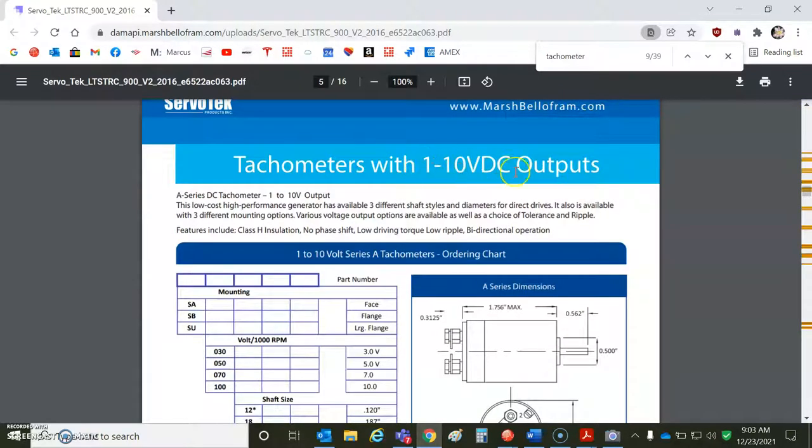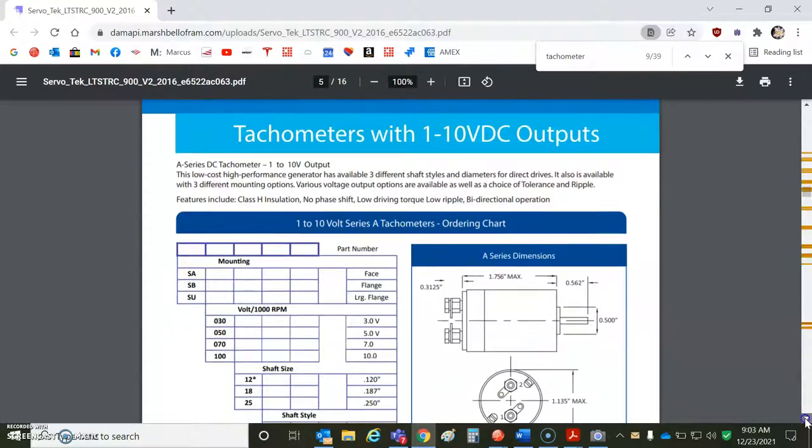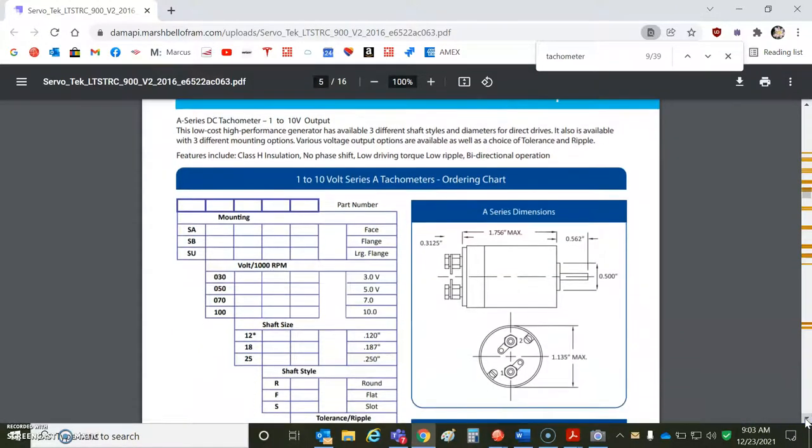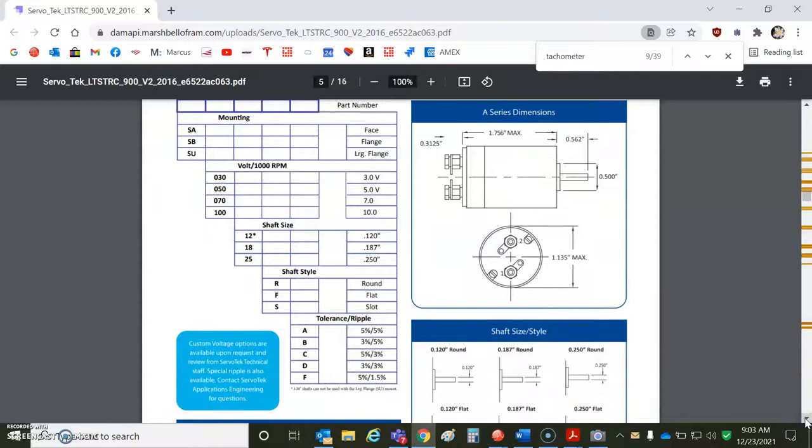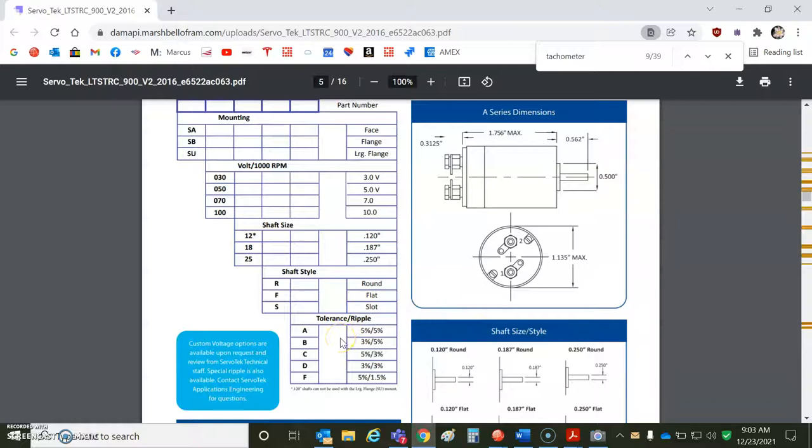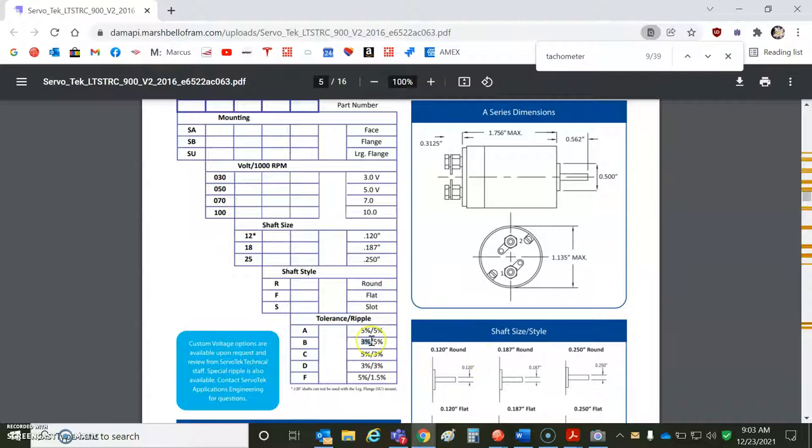Here's a 10-volt output. So when you're spinning at 1,000 RPM, you get 10 volts. That's good for scaling a tachometer to our 10-volt input if you want to go 1,000 RPM. But if you want to go 3,000 RPM, you'll need to put some resistors in line. But you can specify the tolerance or ripple so you can get tighter tolerances of the voltage.